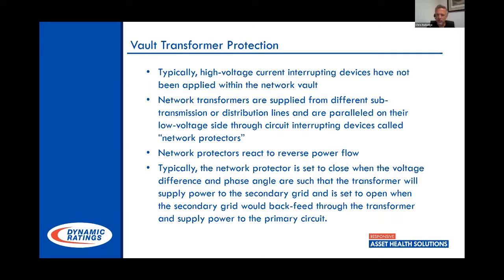They do have protectors on the low side. However, these aren't really to prevent any kind of fault from the high side of the transformer. These are just there to put that transformer into where it's injecting power into the system, or it is locked out of the system, to prevent reverse power flow coming back from the grid through the transformer.